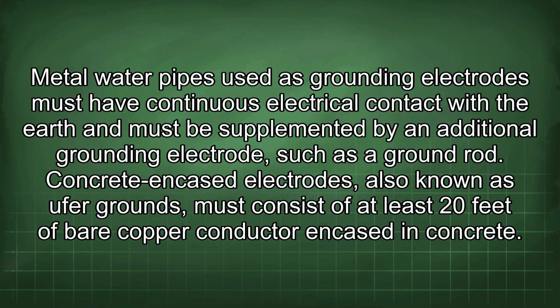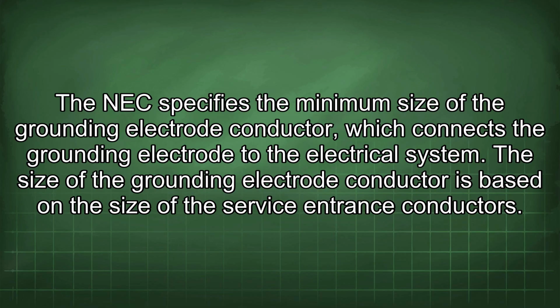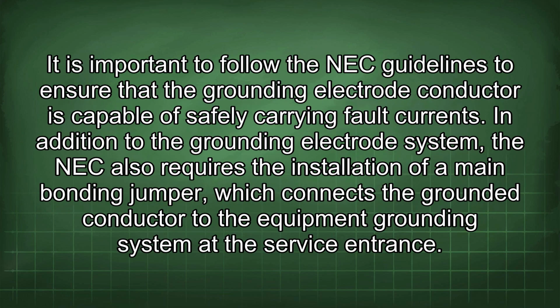in concrete. The NEC specifies the minimum size of the grounding electrode conductor, which connects the grounding electrode to the electrical system. The size of the grounding electrode conductor is based on the size of the service entrance conductors. It is important to follow the NEC guidelines to ensure that the grounding electrode conductor is capable of safely carrying fault currents.